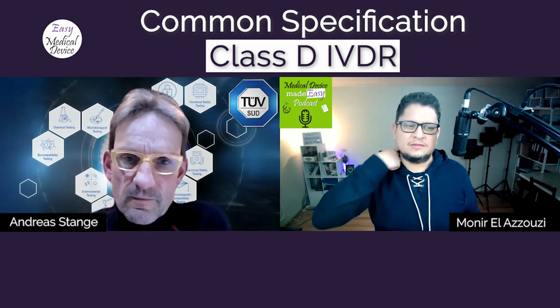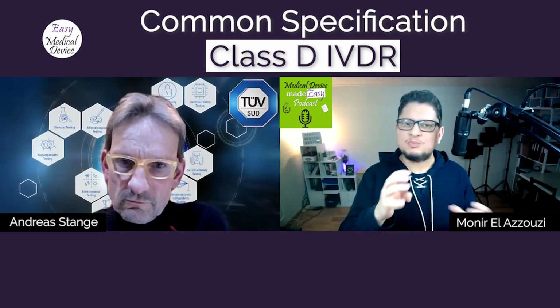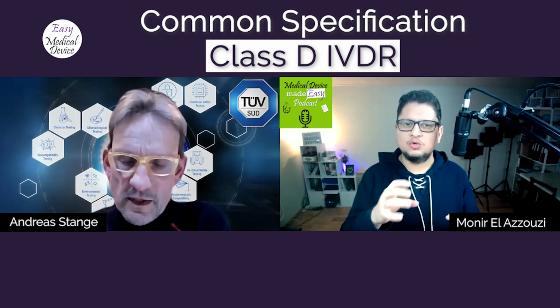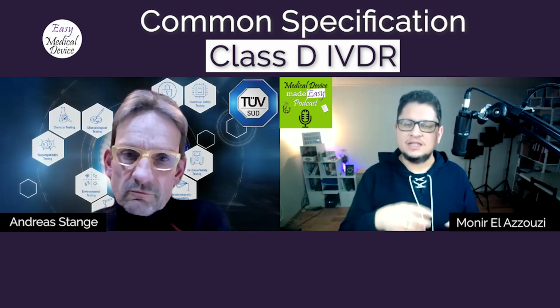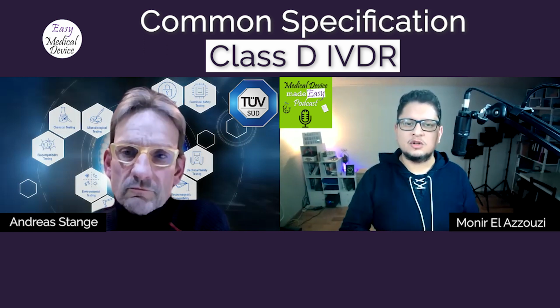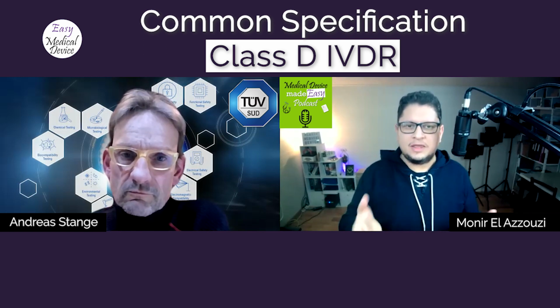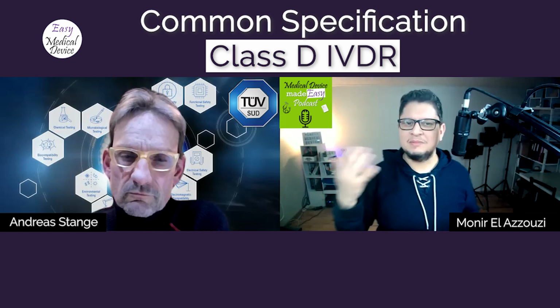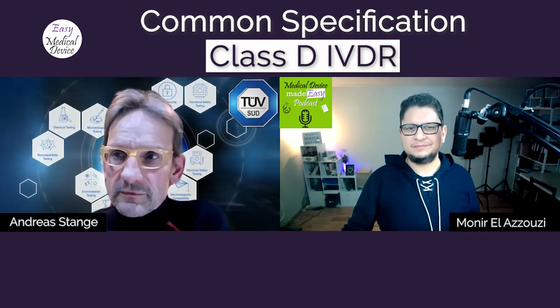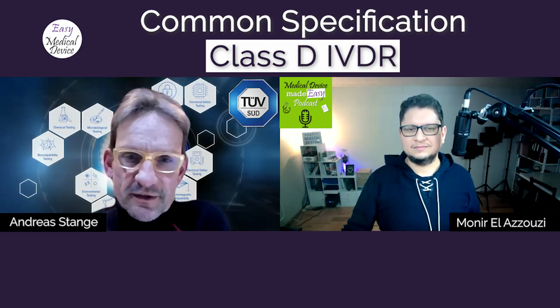Do you think that from now, manufacturers can already look at this draft and say, okay, let's apply these rules? Because inside the draft, it says exactly which parameters they have to look at for each of the sensitivity, specificity, or whatever that is on the product. So can they look at it now, or do we expect some changes of those parameters? Yeah, I don't expect any major changes. No, it would be a smart idea to look at it now.